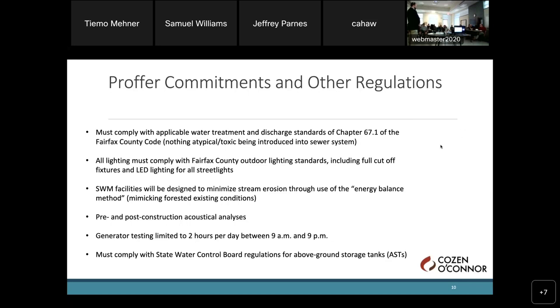So you just said 2 to 2.5? I said the sound level data I had from some vendors was based on a 2.5 to 2.75 megawatt unit. But typically the way generators are purchased and specified is that regardless of sizing, there'll be a sound level specification with them. In this instance, these generators were modeled using a sound level specification of 85 decibels at 23 feet, so that specification could be carried forward to a generator of a 3 megawatt size or smaller to ensure the sound emissions predicted here are consistent with what's experienced down the road.